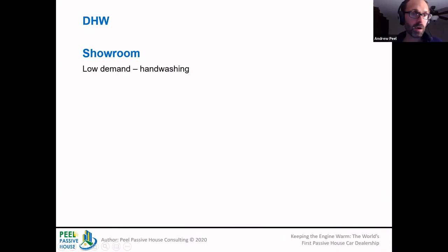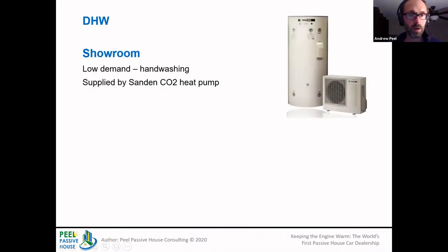On the hot water side, there are two uses. In the showroom, we had hand washing, and in the little washrooms they had, this was supplied by a CO2 heat pump. We decided to install the outdoor unit in the repair shop so that we get a bit of free cooling from that.